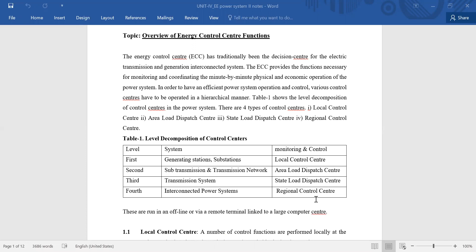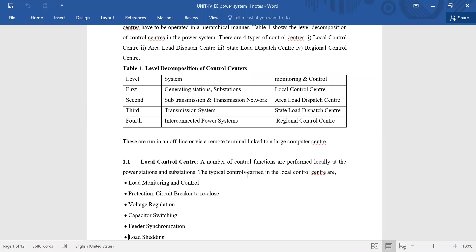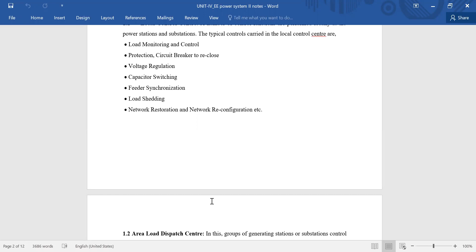First, we are talking about the local control center. The local control center has the generating station and substation, first level. A number of control functions are performed locally at the power stations and the substations. A typical local control center has load monitoring and control. It has protection: if a fault occurs in a transmission line, the relay will send the signal to the circuit breaker and the circuit breaker will trip off. Then we have voltage regulation, capacitor switching, feeder synchronization, load shedding, and network restoration and network reconfiguration.